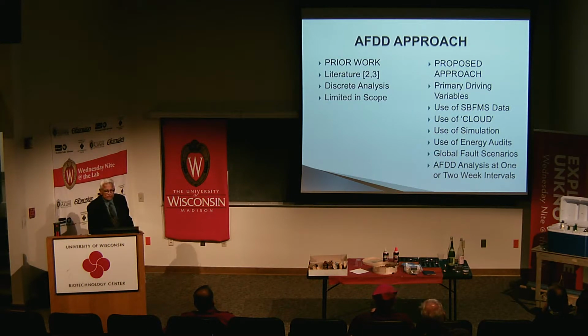Now I'm using, just like before, smart building facility management data, I'm using cloud. Another thing I'm using is energy analysis simulation for the building. The energy analysis simulation can tell us the optimal supply reset point, the monthly cooling energy consumption, the weekly energy consumption by end use, how much for lighting, how much for chillers, how much for fan units, and how much energy for the year. Another important thing is we need good energy audits specific to AFDD, because AFDD depends on the accuracy of the performance and the characteristics of the components, such as the characteristic of the damper and the characteristic of the valve.